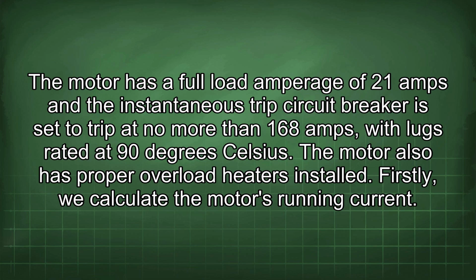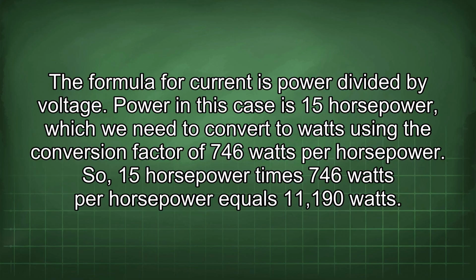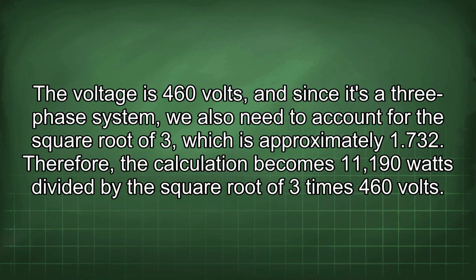Firstly, we calculate the motor's running current. The formula for current is power divided by voltage. Power in this case is 15 horsepower, which we need to convert to watts using the conversion factor of 746 watts per horsepower. So, 15 horsepower times 746 watts per horsepower equals 11,190 watts.